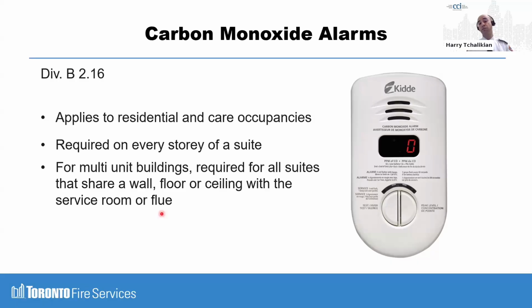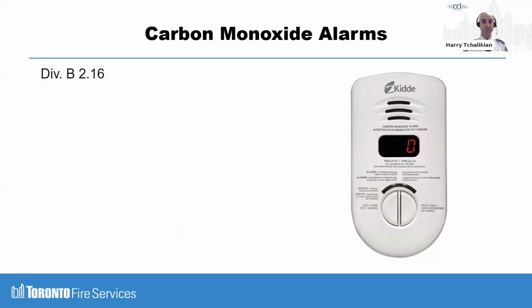What is a flue? It is a defined term in the fire code. It is the exhaust duct of the fuel-fired appliance. So we understand that the service room in an apartment building, if it's sharing a floor, wall, ceiling, then all the dwelling units that share a floor, wall, ceiling need a carbon monoxide alarm. Now, we're also addressing the fact that you may have an exhaust duct running through the building adjacent to other units. Just in case a leak develops, those units also need carbon monoxide alarms. So that's the first set of changes there.